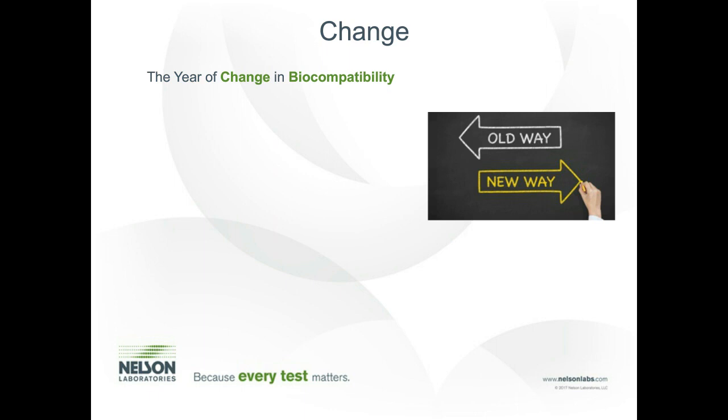Where I see most of the concern, and where we'd like to evaluate a lot of our risk, is with residuals from the processing of these medical devices: oils or detergents or just unknown things that are left behind either from you or one of the suppliers of your materials in that manufacturing process. Because of this concern, we've gone into a checkbox mentality, and now we're going from that checkbox mentality to much more of a risk-based approach, and that's what we're going to be talking about today.